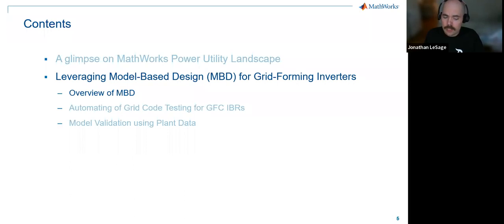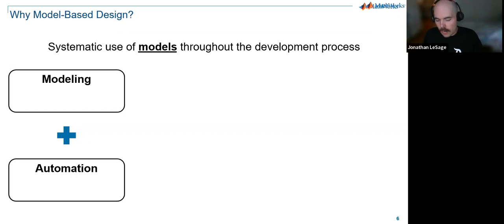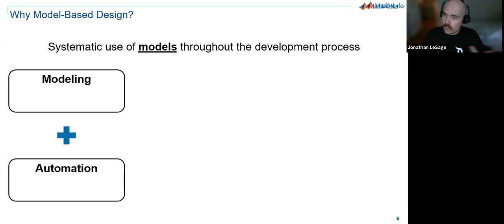Model-based design is the idea of leveraging models — whether first-principles models created using equations or schematic representations — but also being able to automate and streamline things throughout the process. As we've seen increased grid codes — IEEE 1547, 2800, ERCOT-specific requirements — being able to automatically test all these different grid codes and validate that commissioned systems actually adhere to all regional requirements is one of the key things we'll show today.